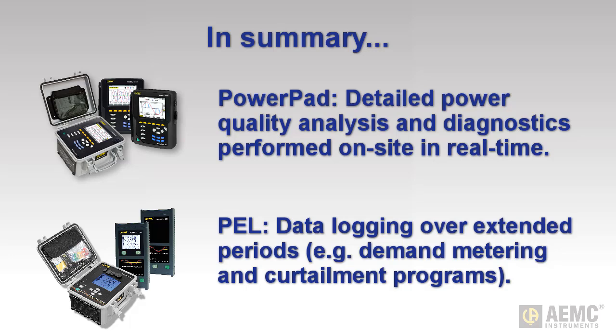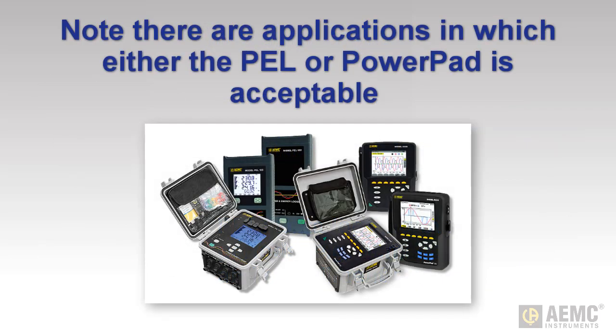A wide range of connectivity options enable you to build global networks of centrally controlled instruments. You can perform long-term data logging and monitoring of trend data, which can then be downloaded to a computer for analysis and troubleshooting. Typical applications for the PEL include demand metering and curtailment programs that often require extended recording sessions. Bear in mind that both PowerPad and PEL are versatile and share a number of capabilities — PEL does offer limited power quality analysis, while PowerPad can perform data logging, and there are many applications in which either instrument would be well suited.